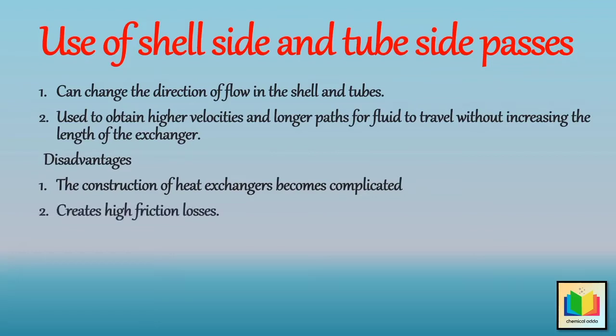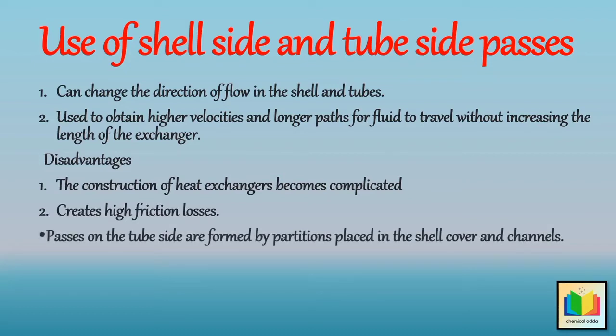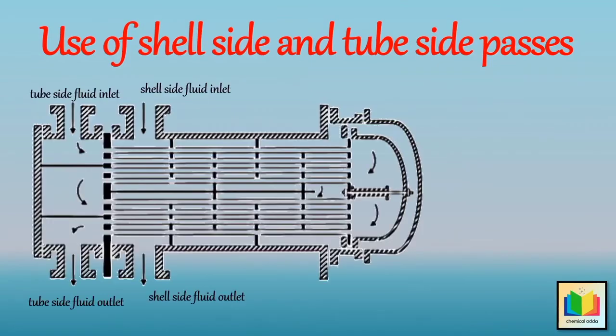Passes on the tube side are formed by partitions placed in the shell cover and channels. When we use a single pass partition on the tube side, the tube side fluid flows twice through the heat exchanger. Hence, the pass partition divides the tubes equally into two sections.